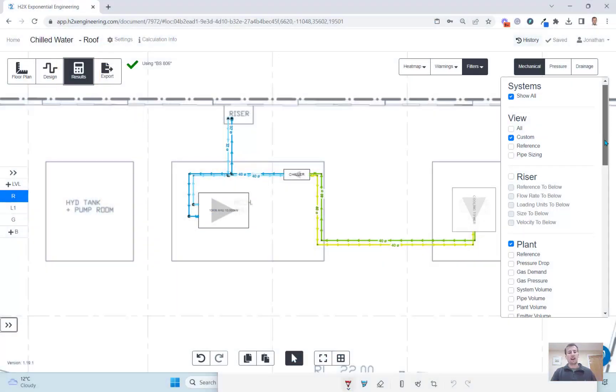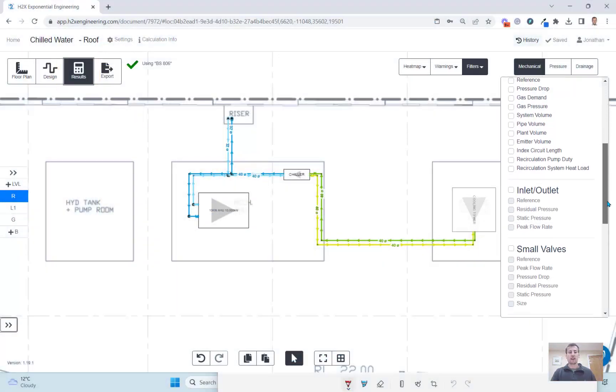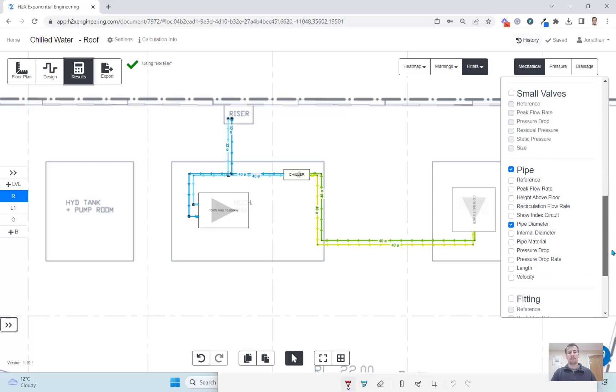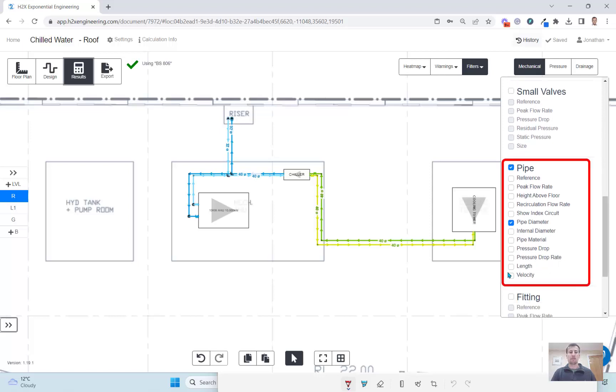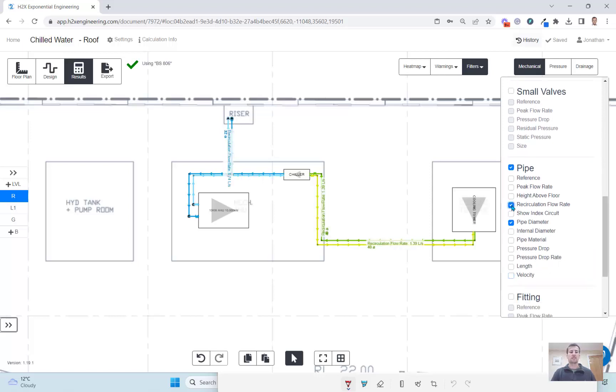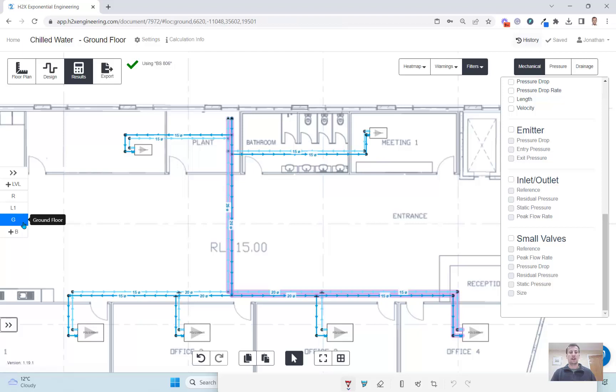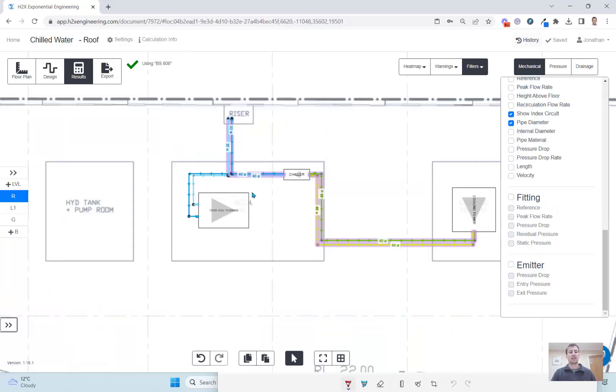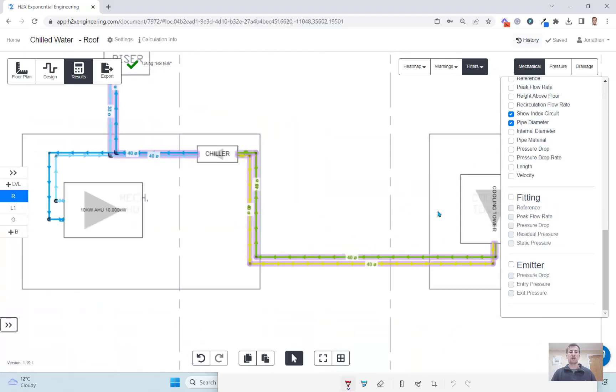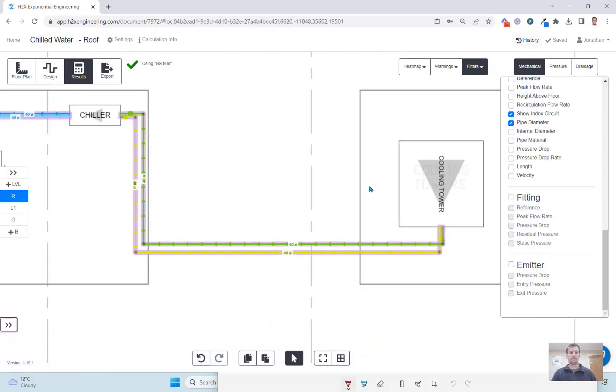There are a range of results available and first we'll focus on the pipes. Here we can see the pipe diameters and then we can choose to see the velocity, flow rate and pressure drop rate on each pipe. You can also highlight the index circuit and follow that through the whole system.